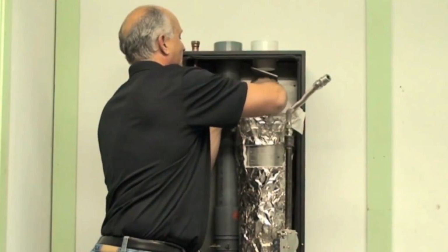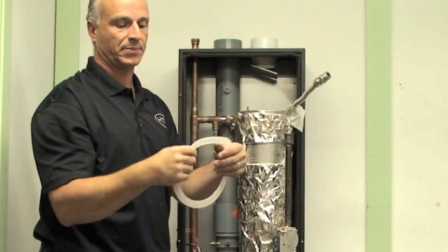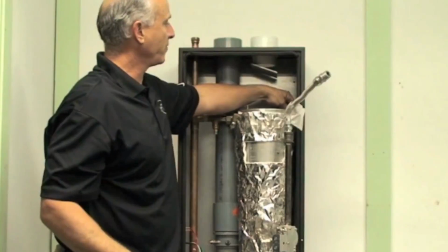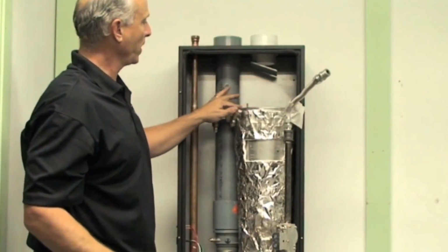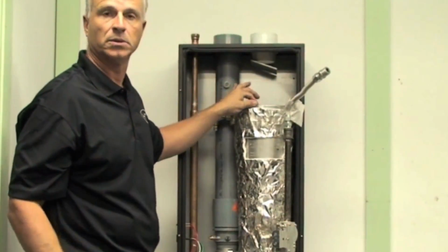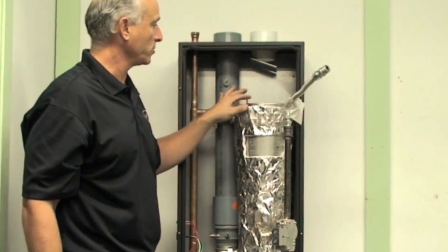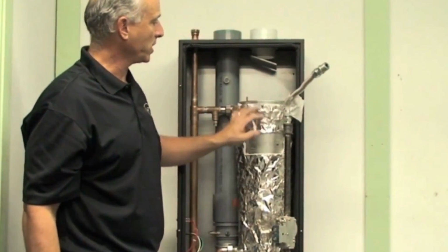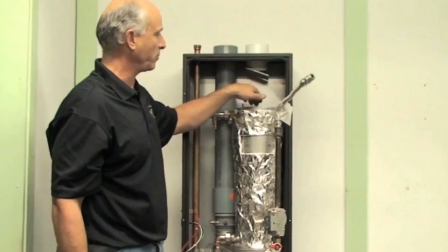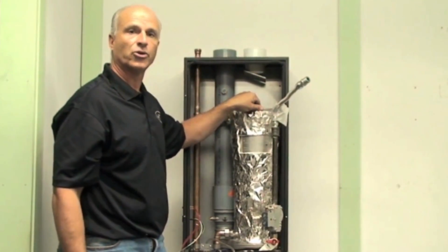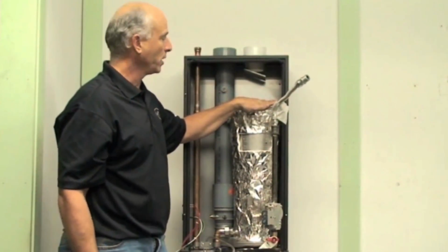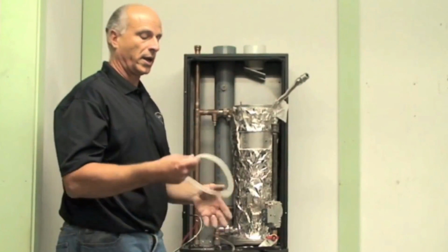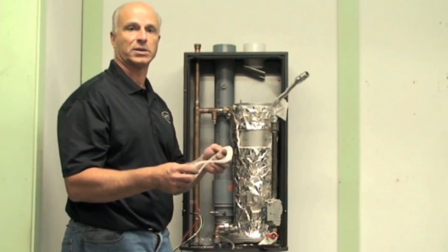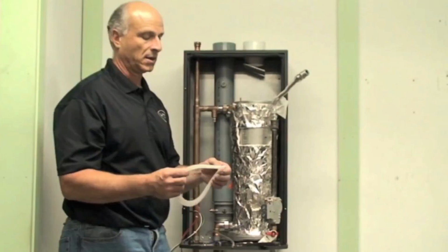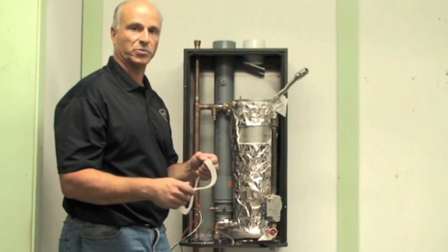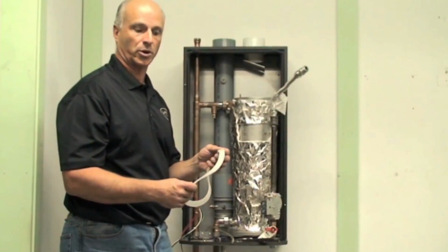One of the things I want to point out, the reason why this is a high temperature silicone, the reason why that's very important is this whole flange here is water cooled, which is different than the other boilers. So the water jacket actually extends into the combustion chamber. So this is all water cooled. So it should keep the components cooler, it should keep the door cooler, and it should make the gasket last a long time. Heat is what kills gaskets. So it won't become embrittled and the seals will be very good for a long period of time.